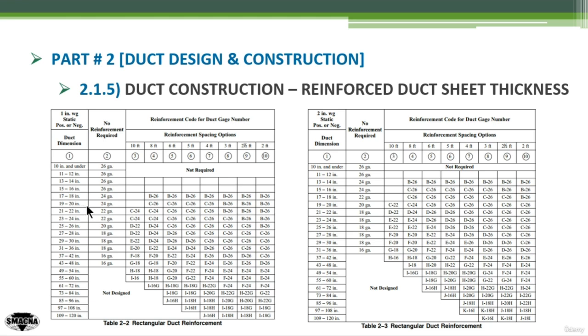For the height — the second dimension of the duct, the 20 inch — I can use gauge 24 without reinforcement. Or if I want to use reinforcement, I can increase the gauge to 26. Given 5-foot reinforcement spacing, I can use reinforcement class C with gauge 26.